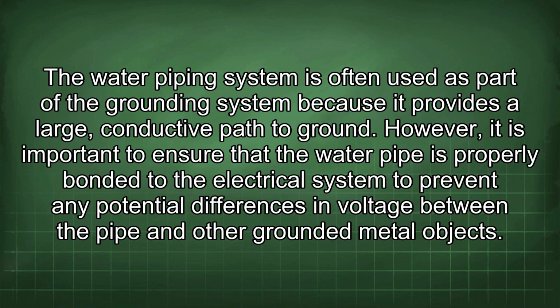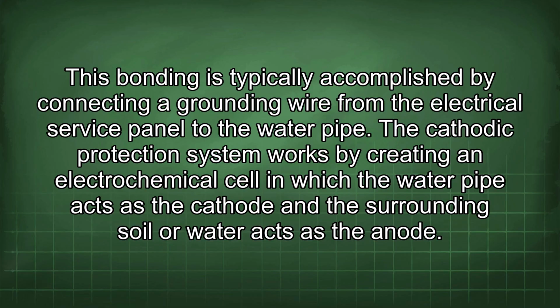The water piping system is often used as part of the grounding system because it provides a large, conductive path to ground. However, it is important to ensure that the water pipe is properly bonded to the electrical system to prevent any potential differences in voltage between the pipe and other grounded metal objects. This bonding is typically accomplished by connecting a grounding wire from the electrical service panel to the water pipe.